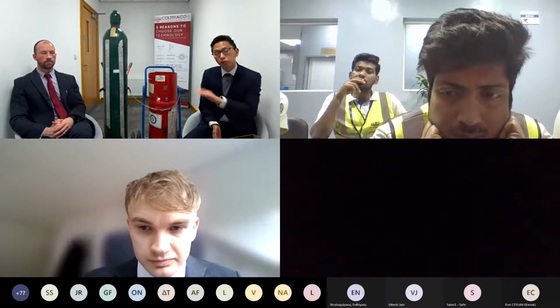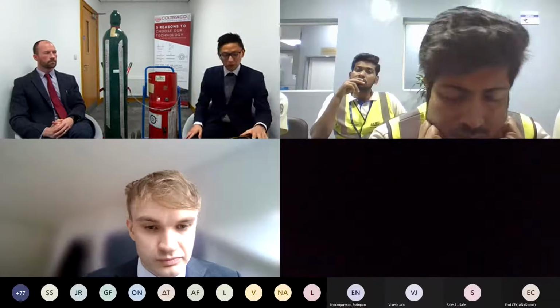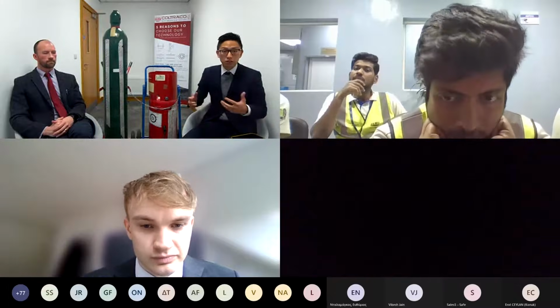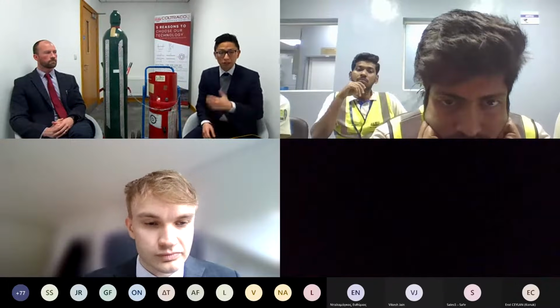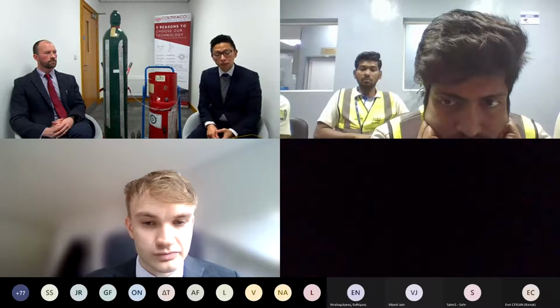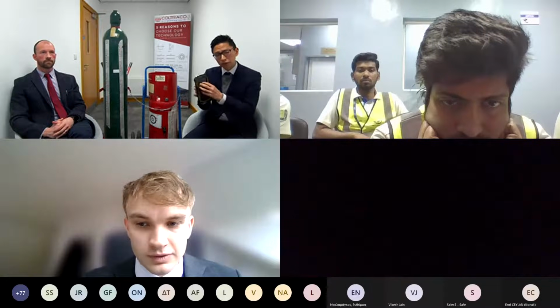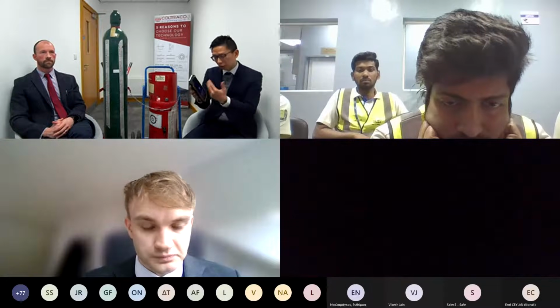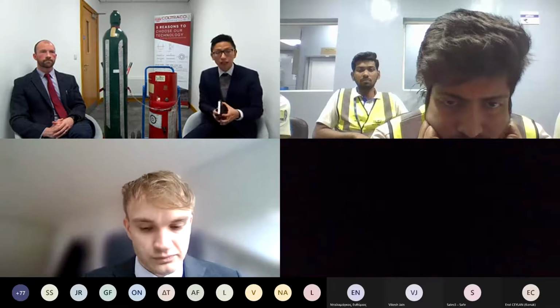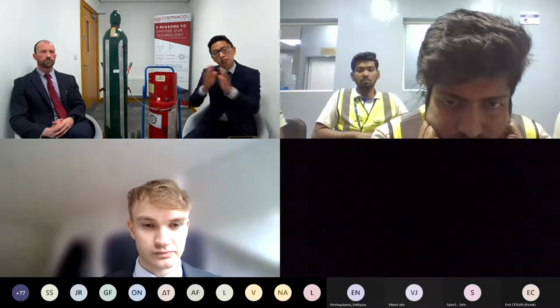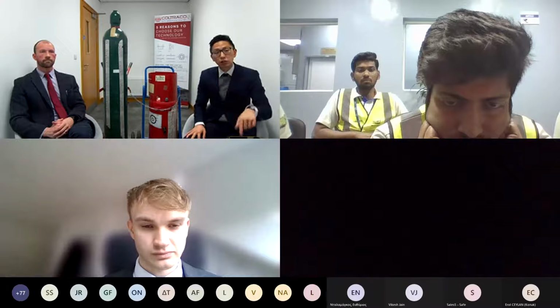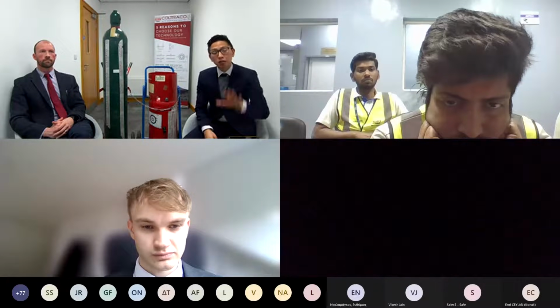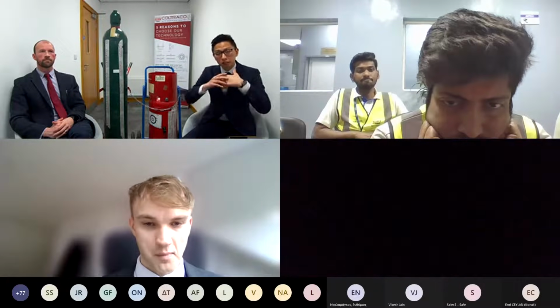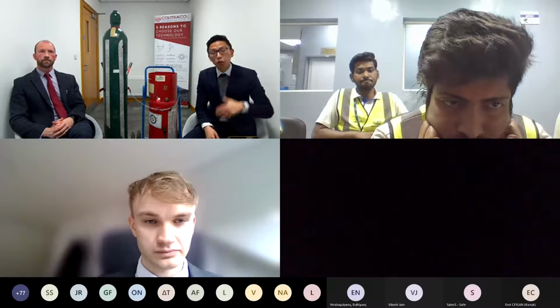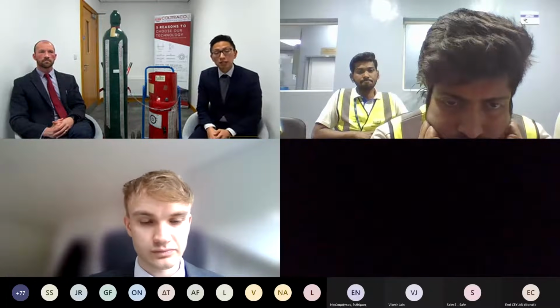The reason is, well, during this demonstration, this room at the moment is about 15, 16 degrees. So I think what you're referring to is in the Portasteel, when I showed the temperature range, it's actually minus 20 to 30, but the minus sign on 20 was probably not clear on the camera. That is the entire operating range where CO2 will exist as a liquid.